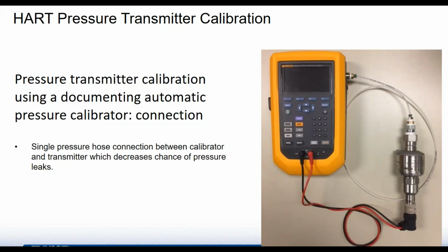So here's your typical connection. That little silver looking thing on the side there, that's actually a mounted pressure transmitter. It doesn't have all that fancy blue casing for outdoors. This is more of a lab type setup transmitter, nice and small. But you can see, I've got my wiring from the calibrator going to the transmitter, and just one line going from the pressure sensor in the transmitter right to the pressure port of the calibrator. So just having a single line makes it a lot easier. Less chance of pressure leaks, and of course, with that calibrator, we've got the built-in pressure regulator and pump.